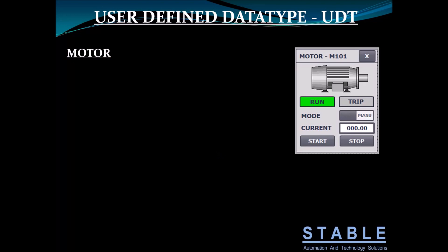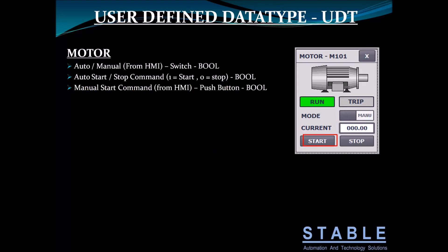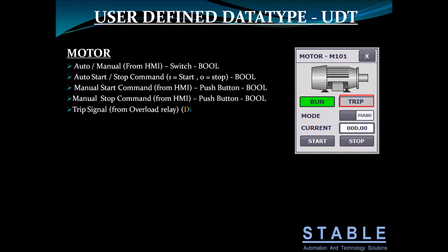For example, in our motor we have auto and manual modes that we change from the HMI, along with start and stop commands. When you put the motor in auto, your logic will decide to start and stop the motor. But when you put the motor in manual, you can start and stop it from the HMI or the plant. A trip signal comes from the overload relay, and a run command is a digital output.